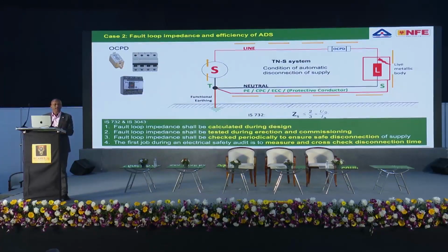A very important subject. Now, an important point I wanted to tell you is that not only the National Electrical Code, but also the Central Electricity Authority regulation, which is generally followed by the Electrical Inspectorate, has written very clearly. So in future, electrical inspectors will start asking you to show the test report, the fault loop impedance test report. This is going to come.